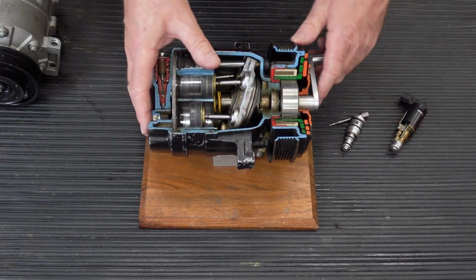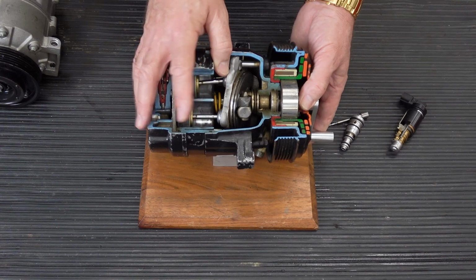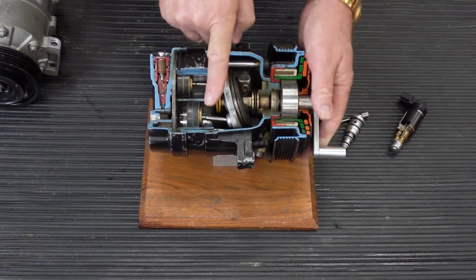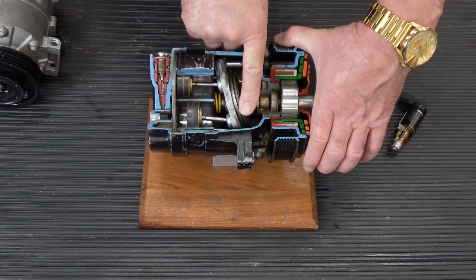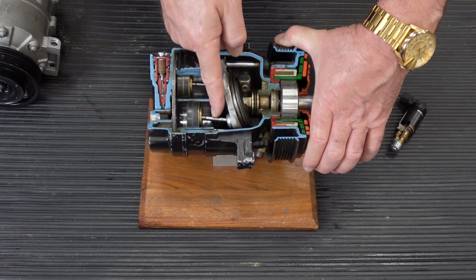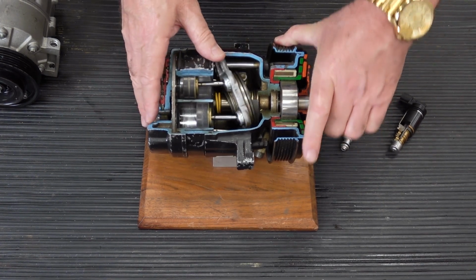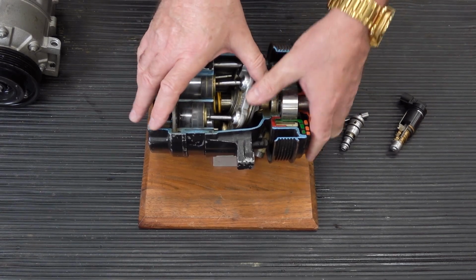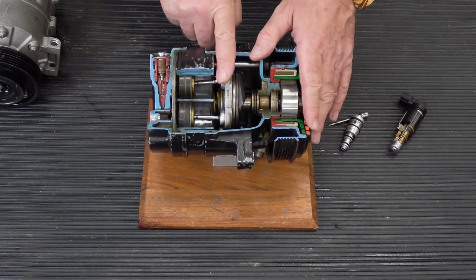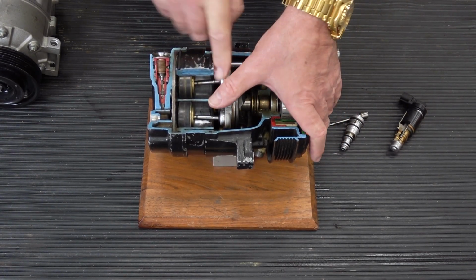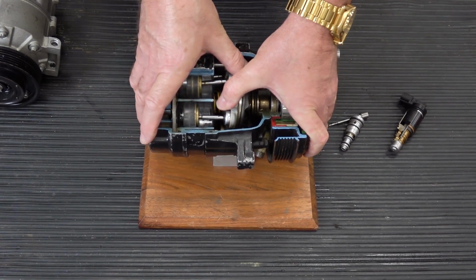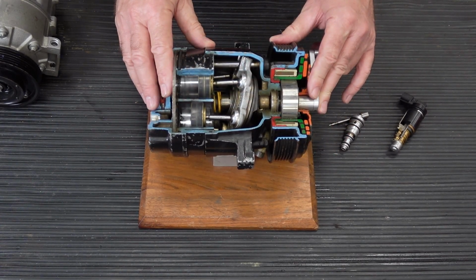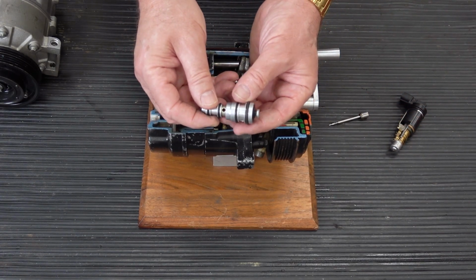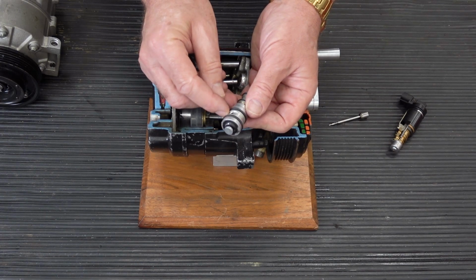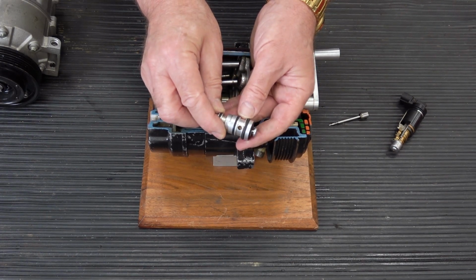And the way this works is that by bleeding pressure into or out of the crankcase of the compressor, I change the pressure difference across the pistons, and that way I can change the angle of the swash plate seamlessly, gradually, smoothly, on the fly, to change the pumping displacement of the compressor to match the heat load in the system. The problem, of course, is that this compressor really has only one input. The only thing it can sense is suction side pressure.